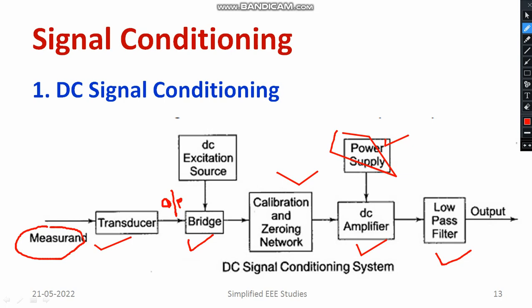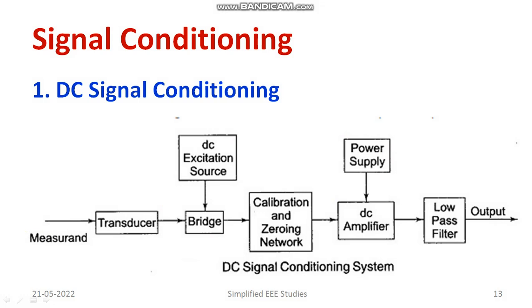Afterwards, the signal is connected to the calibration network, where proper calibration and zeroing are performed. The signal then needs to be amplified, so a DC amplifier is used to increase the amplitude. To operate the DC amplifier, we need a DC power supply. The output of the amplifier contains high-frequency signals and noise that need to be filtered out using a low-pass filter before connecting to data acquisition devices or the output.